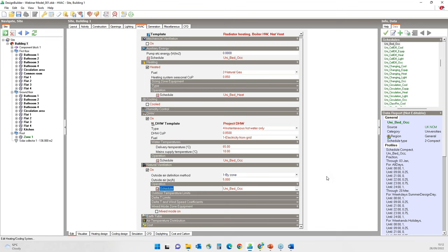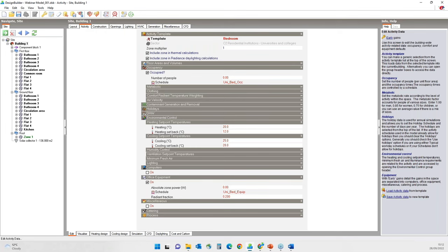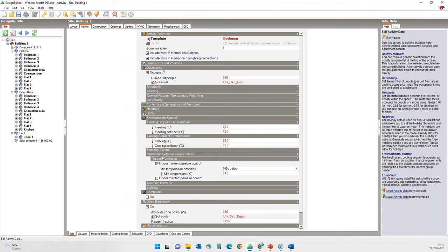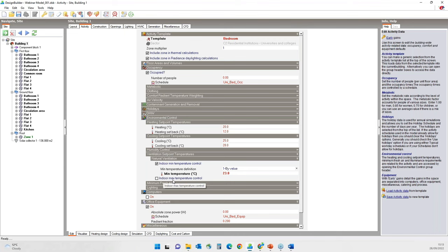Note that you can switch between SI and IP units in the program options. Moving on to the activity tab: here you can control the operation of natural ventilation based on indoor temperature set points. Under the ventilation set point temperatures header, I will change the natural ventilation minimum set point to 23 degrees Celsius — so natural ventilation will be switched on only when the indoor temperature is above 23 degrees. I will leave the heating set point at 20 degrees Celsius, which should provide a sufficient band to prevent simultaneous heating and ventilation.